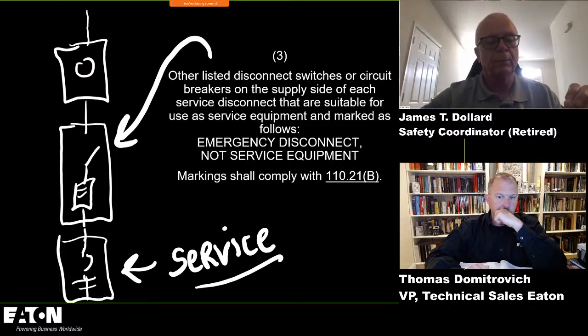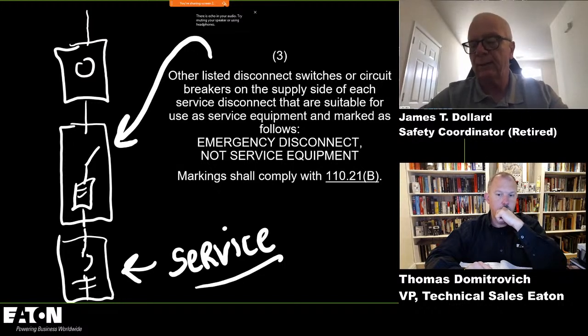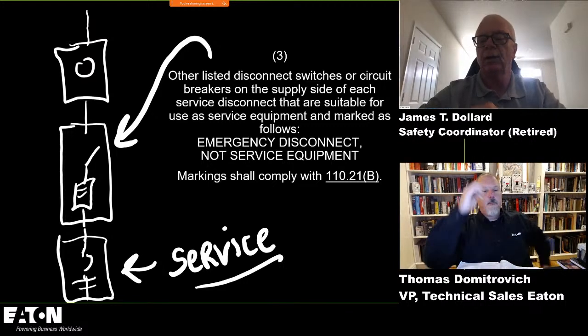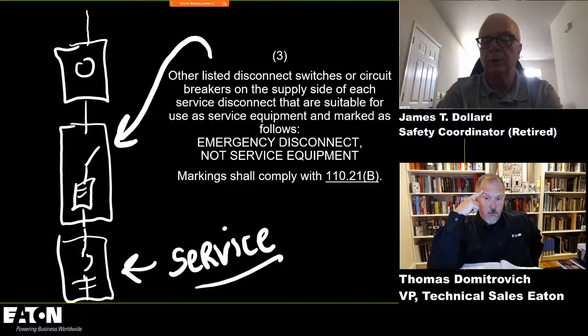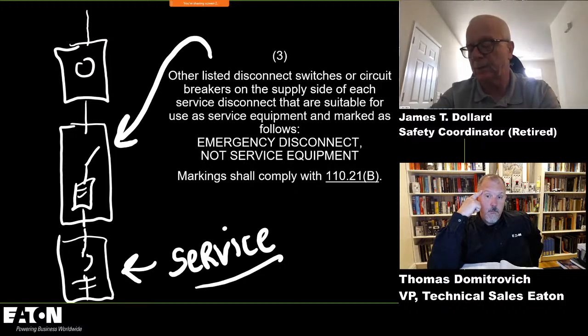But we didn't want it to be the service disconnect, because we didn't want to require you to take a grounding electrode conductor in there, and we didn't want to require you to take SER into the building. That would also impact service upgrades. A service upgrade would be a little different if we allow you to not call this disconnect your service disconnect, but call the main in your panelboard. As soon as you land in that panelboard or load center, you can combine your grounded conductors and your equipment grounding conductors. So there was a lot of thought that went into this. When you take it apart and lay out what's required if we don't do this, then look at both methods and ask what the net benefit is, there is none. There's no net benefit to mandating that it be considered service equipment.